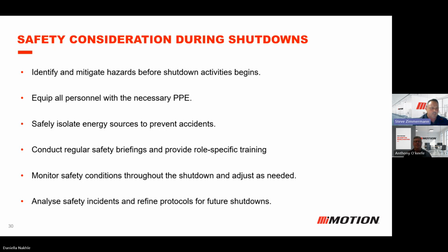When we actually get on the job, it's around isolating. We want it to generally be the people or the client's responsibility to isolate the machinery because they know their machinery. When it's isolated, it's our job to put our lock on, to verify that equipment is not live anymore, check the paperwork, and confirm the isolation procedures have been signed off for that day, and that we have the go-ahead to start that shutdown or replacement of machinery, depending on what it is at the time.